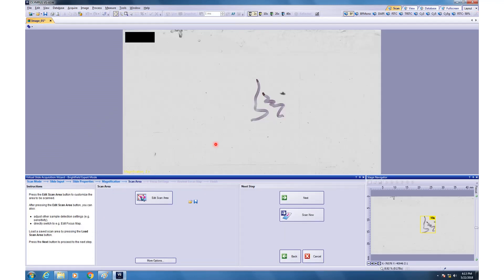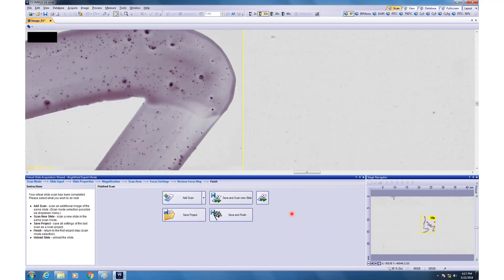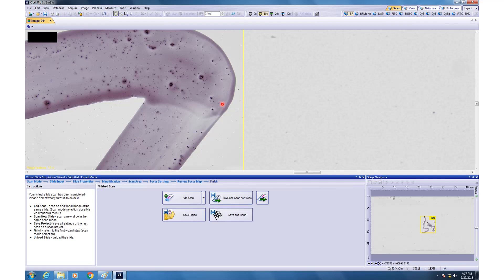Now, you are all set to start the imaging. You can click scan now. After the scanning is done, you can zoom in as much as you want. Just like Google Maps, this area you can consider as village and this area you can consider as city. This is actually a merged image where there are two different layers, 10x image and 2x image. You can see definitely this is less noisy and this one has got better resolution compared to 2x. If you are happy with this image, well and good. If you are not happy, you can add more scans and this will automatically take you back to this position.